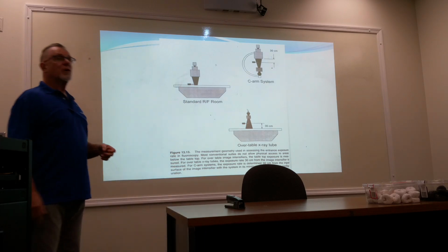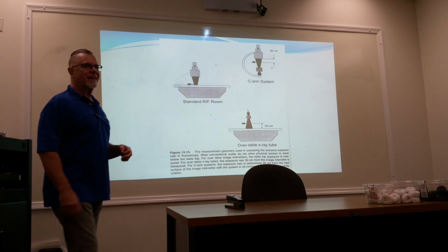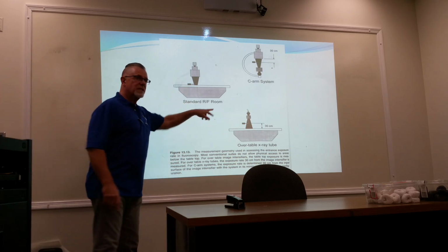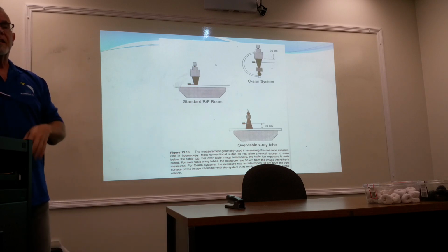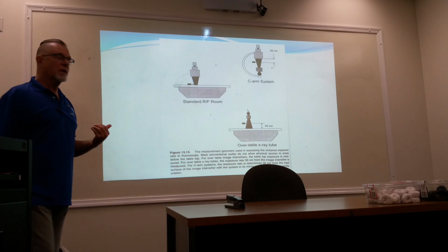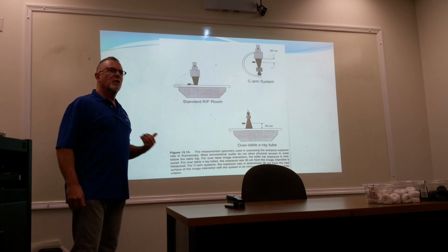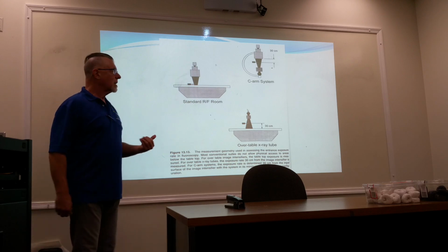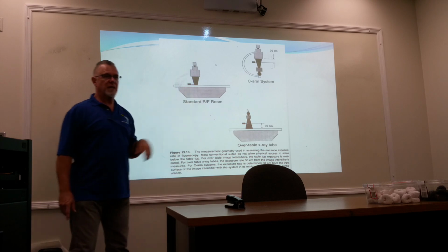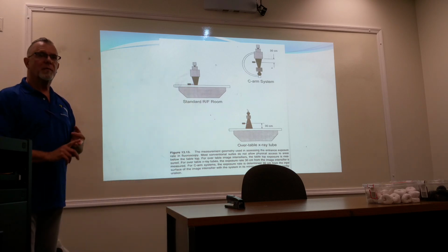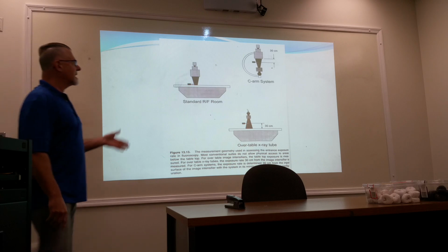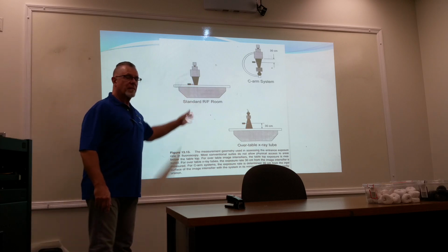State of California and Joint Commission especially says, Joint Commission says every piece of radiation emitting equipment that's brought into an accredited hospital before it is ever used on a patient will go through an acceptance test. Both for image performance, equipment performance, electrical safety, all of that has to be done. Okay?